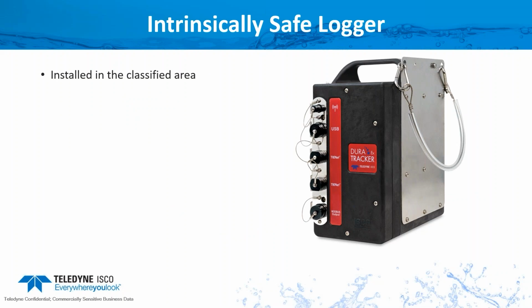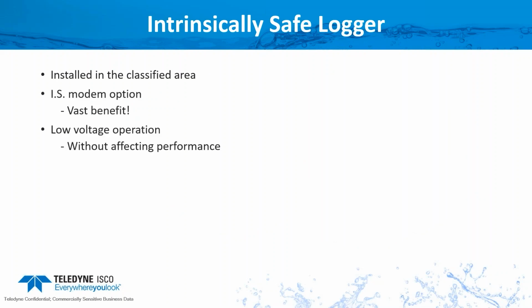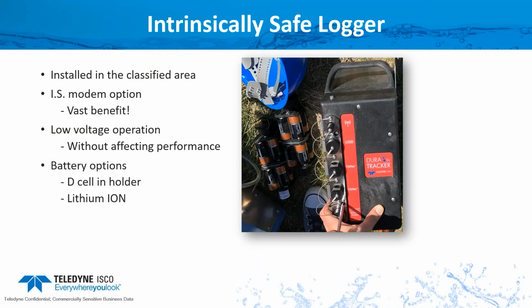That way you don't accidentally connect a non-intrinsically safe sensor into the IS-rated data logger. Now, the DuraTracker EX can be installed in the classified area. It has a modem built in, which is a huge benefit, because if you can avoid going into the pipe or the classified area for any reason, you can just call it up from your office, see what's going on, and calibrate your level remotely through the modem. It has low voltage operation, using D-cell batteries. So we have a D-cell battery holder and/or lithium-ion batteries to power the DuraTracker system.